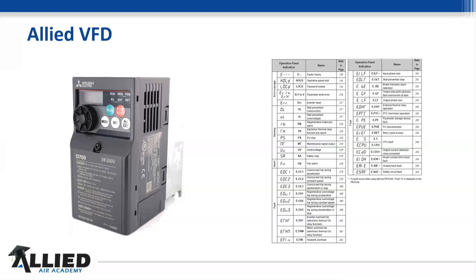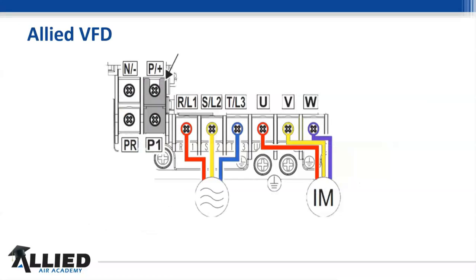It's cutting it off because there's a high amperage situation or there's a dirty voltage situation, and it's going to protect that motor. Because when you look at the actual wiring of the motor, it's not all that difficult, but you do have a phase. Here's the numbers. You can only be on 3-phase plus or minus 10% on voltages, up or down. So it's got to be pretty close in. That's why getting our voltage sheets done is important. The frequency has to stay within plus or minus 5%. And you saw we went from about 40 to 60. Depending on what units you have, that may or may not change, but the phase balance is what's important here.